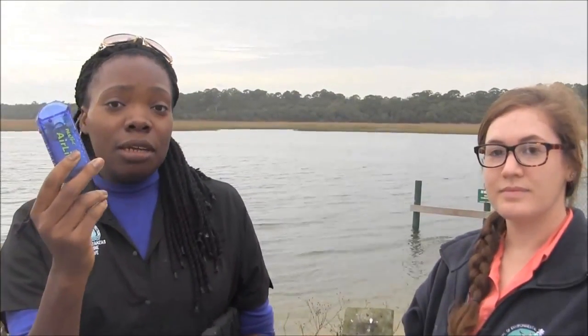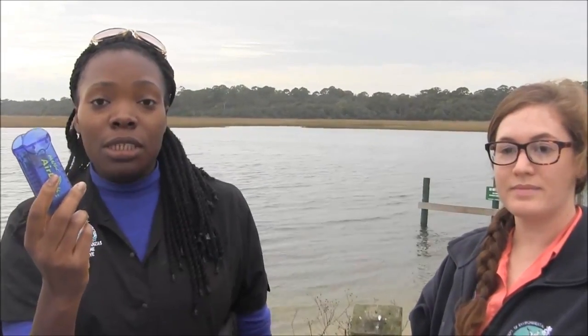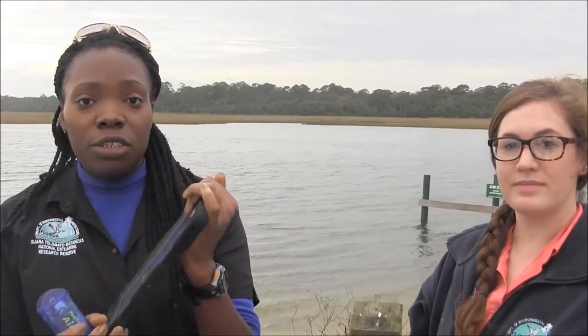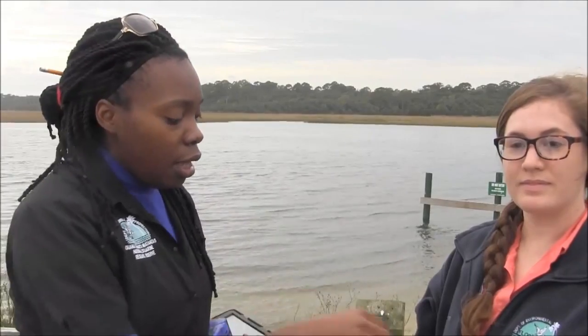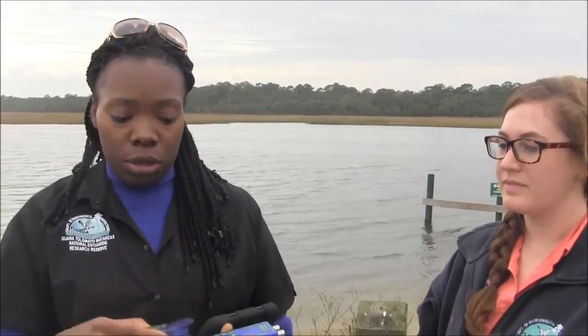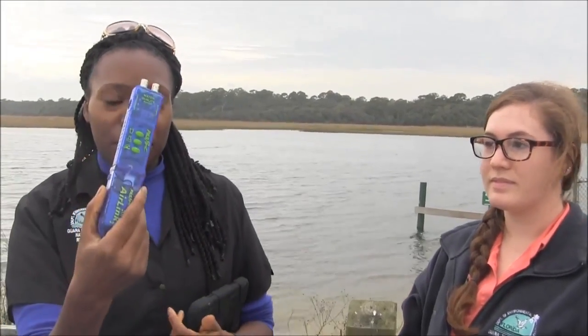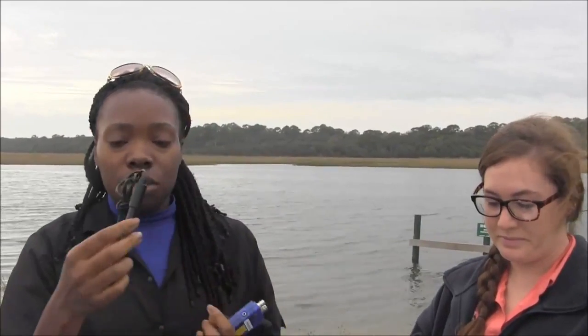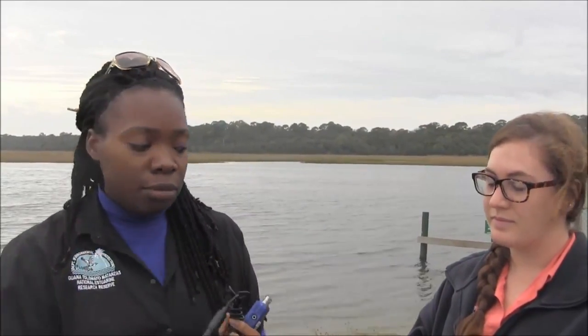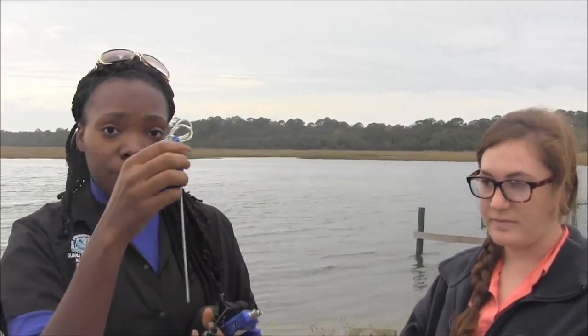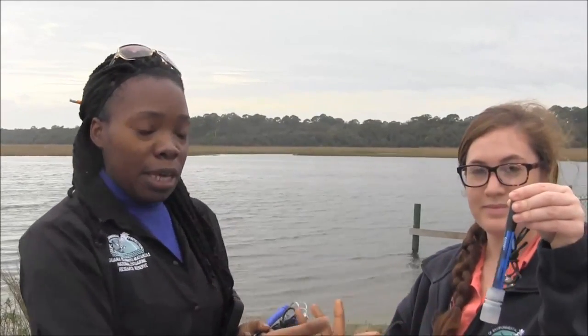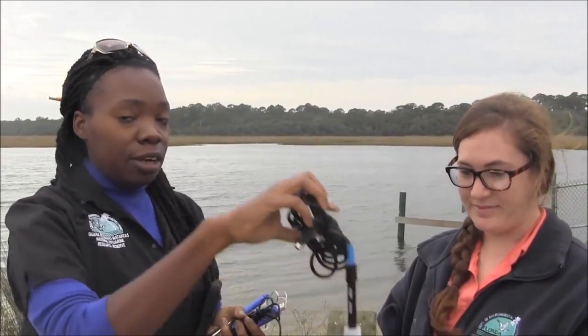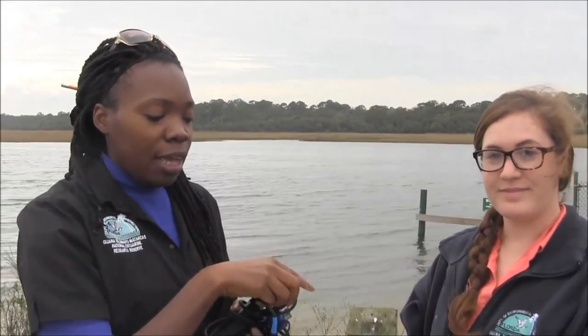This is a device that through Bluetooth wirelessly connects your probe to your smart device so you can actually read what you're collecting. This is your water quality sensor. This is what you're going to connect into your Pasco AirLink 2. You're going to need your conductivity sensor or probe. This is going to be for salinity. You'll need your temperature probe, your pH probe, your dissolved oxygen probe, and your turbidimeter. And of course, you're going to need a helper.